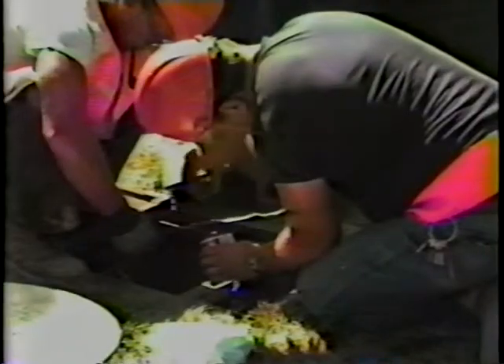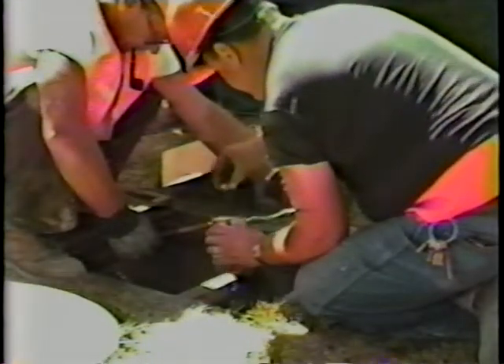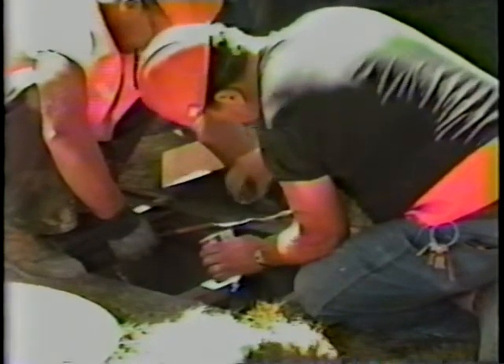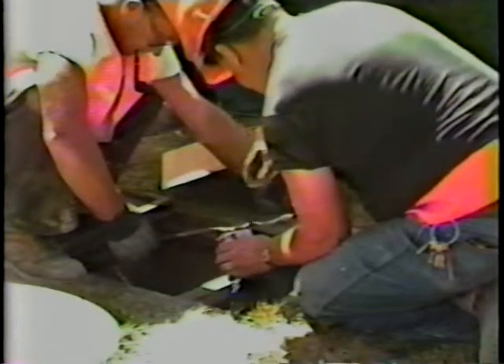Wire splicing in a loop system is done basically in two steps. The first — physically connecting the wire ends — can be done by soldering, a screw and nut, or a crimping method. The second step is to environmentally seal the splice by either applying several layers of various re-insulating materials, or by encapsulating the spliced area in a container filled with embedding sealant.